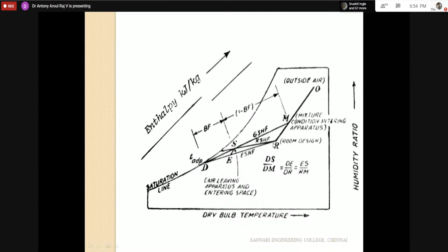So we are calculating the effective room sensible heat: the room sensible heat plus bypass factor into outdoor air sensible heat, then the air conditioning system gain, the sensible component, into bypass factor. Similarly, we have the effective room latent heat: the room latent heat plus bypass factor into outdoor air latent heat, and the air conditioning system gain multiplied by the bypass factor. So I calculate the effective room total heat.